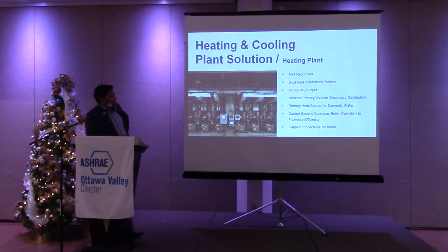Dual fuel condensing boilers, variable primary and variable secondary distribution. So we had variable flow on a primary loop to deal with the varying loads in the building, as well as the domestic hot water system, and then variable secondary distribution to deal with the entire building. We also put the boiler control system in that was connected to the overall building plant.